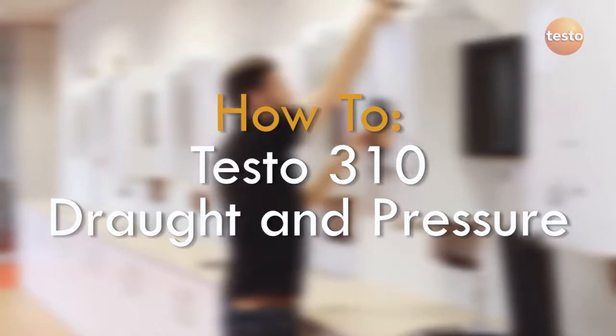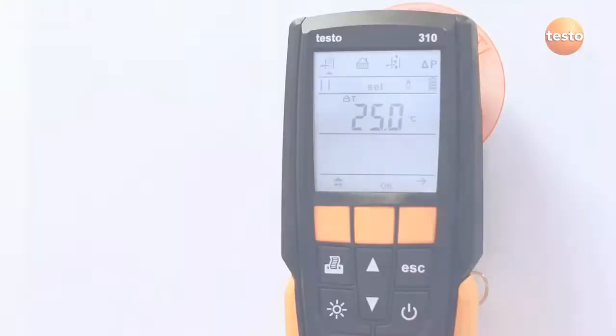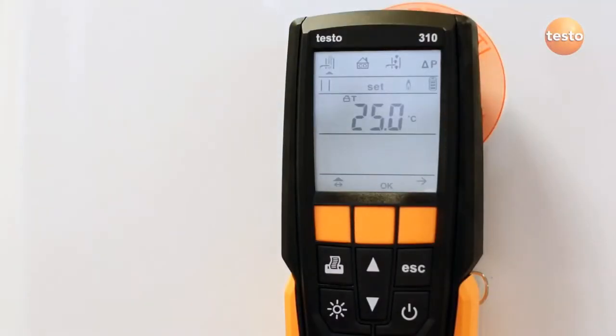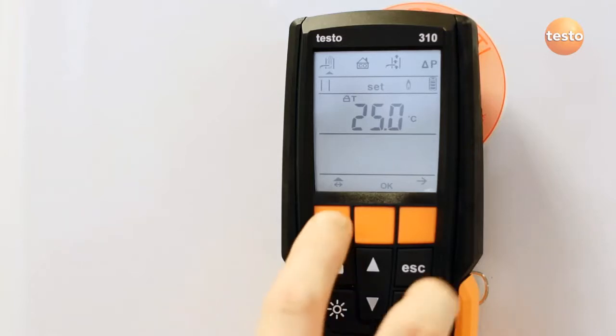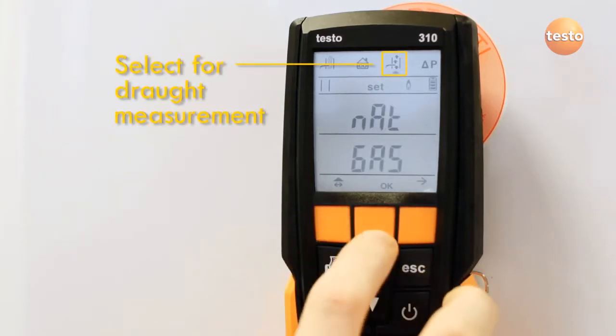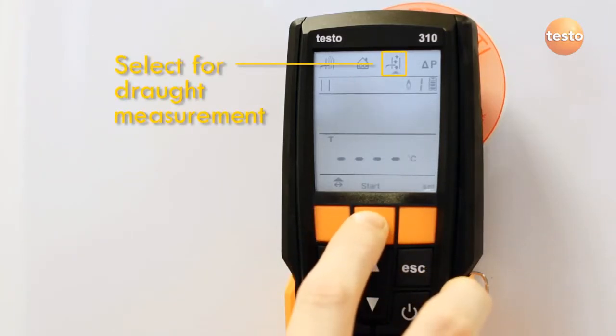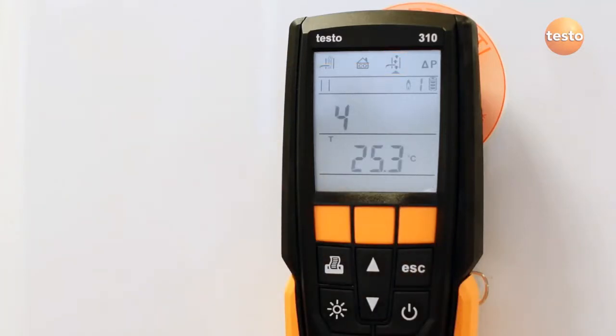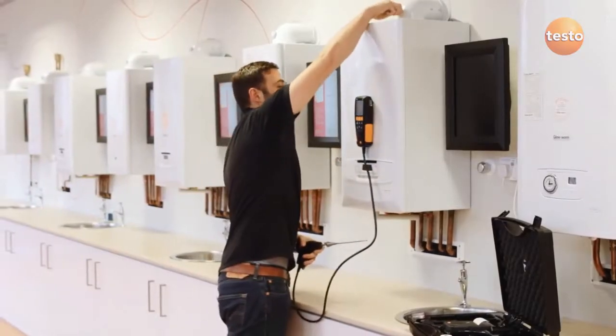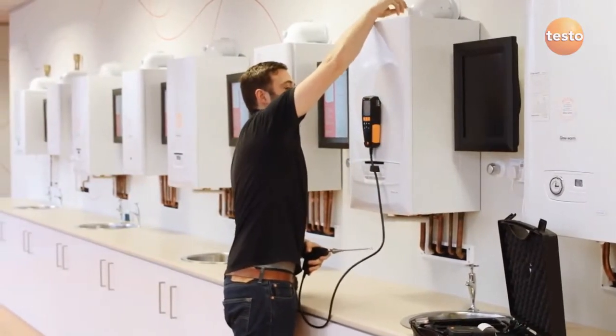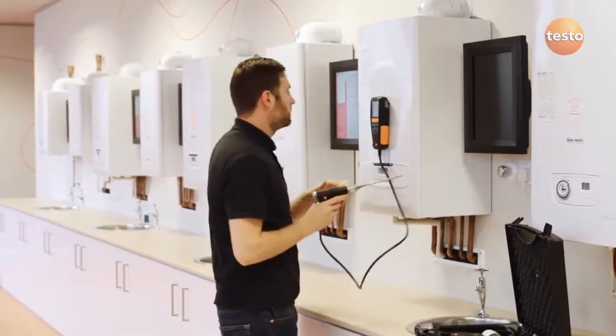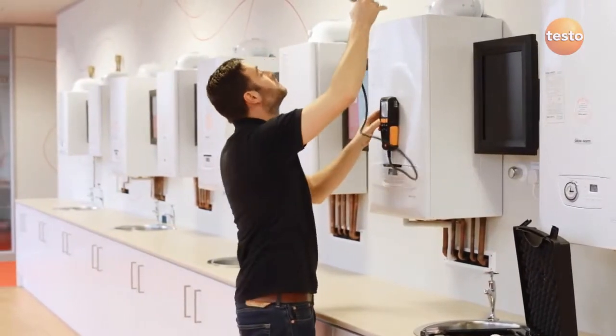The 310 has built-in pressure sensors, which means the analyzer can be used to check the flue draft or to measure gas pressure. To measure draft, select the test on the screen. And then with the probe in fresh air, press start. The pressure sensors adjust the barometric pressure for 5 seconds. It's important that the probe is in fresh air while the pressure sensors are zeroed. Then it's ready for the probe to be put in the flue with the boiler running.